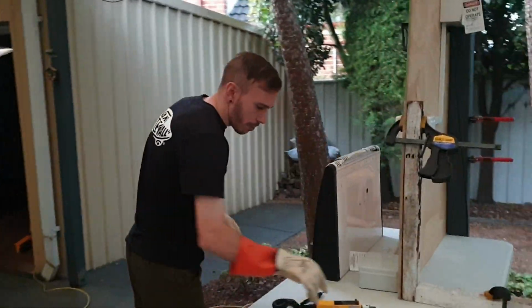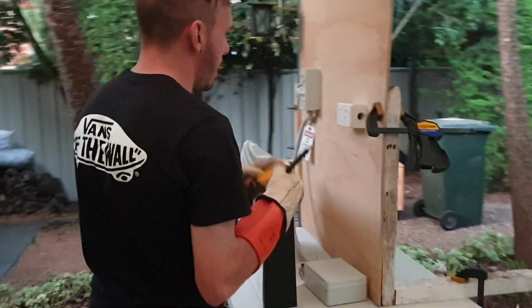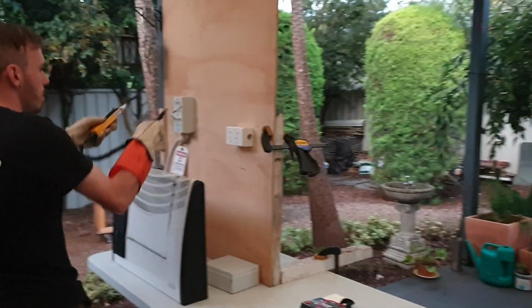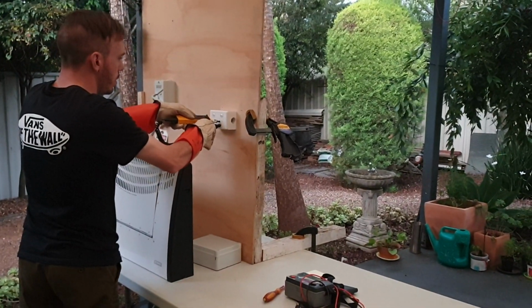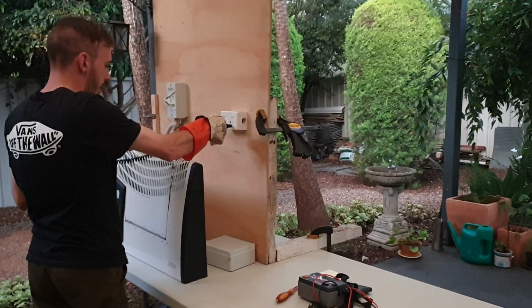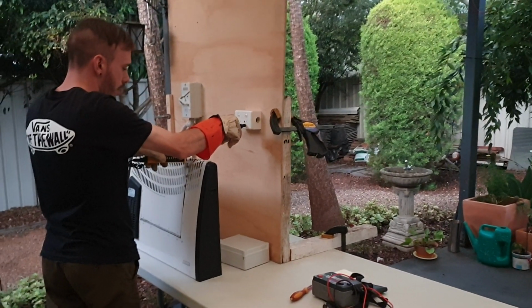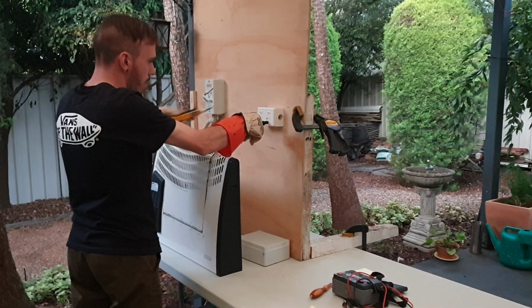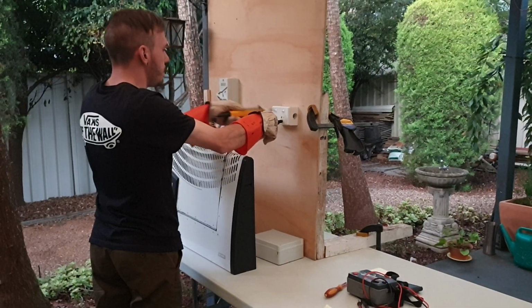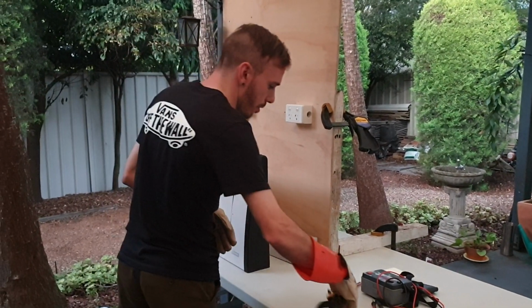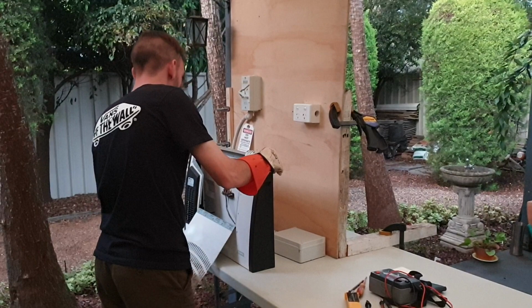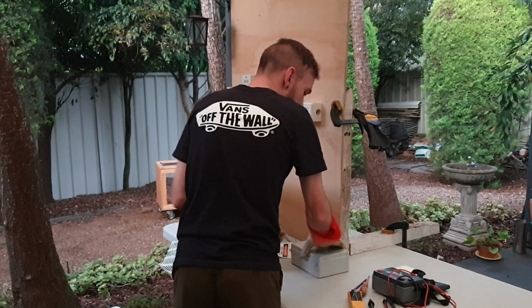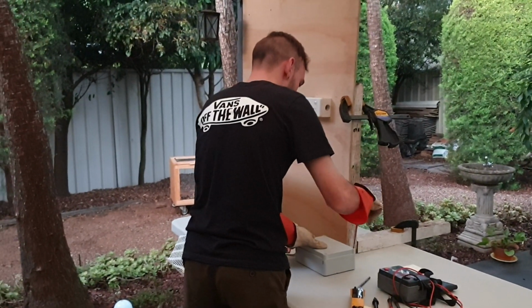Before we begin anything, we're going to first check our meter on a known live source. There's voltage at the known source. Now we're going to test it to the frame, ensuring the frame is still safe. Test at 2 points, retest the meter. So now it's safe to open the appliance. And now we're going to open up the junction box.